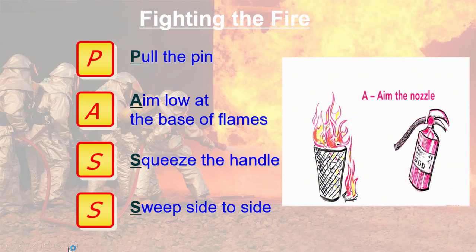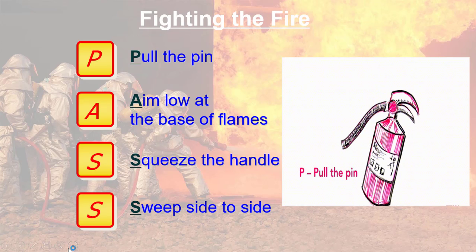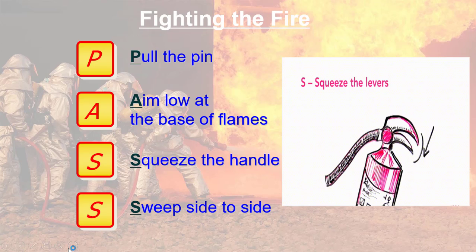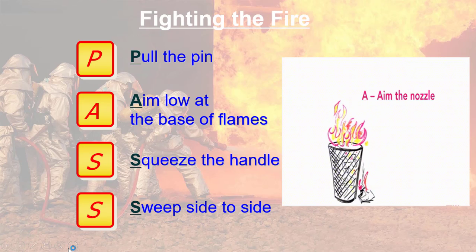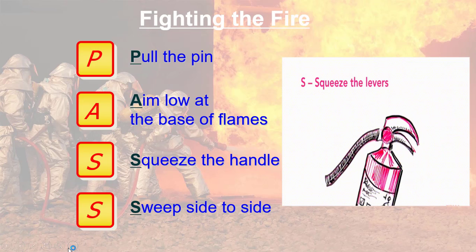Fighting the fire — PASS. P represents Pull the pin: first, remove that safety pin. A represents Aim low at the base of the flame — don't go near the flame; maintain a minimum distance of six feet from the fire to your hand or cylinder position. S represents Squeeze the handle. The other S represents Sweep side to side — make a complete sweeping motion side to side so that the agent makes full contact. This is for liquid fire.